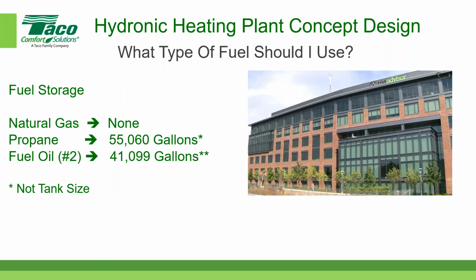And you get that information by talking to your propane supplier, because based on the amount of storage you want on site, they have a calculation, an app that they use to figure out what the size of the tank would be so that the propane creates a certain amount of surface area inside the tank so that it evaporates at the right rate, especially relative to whether the propane tank is buried in the ground or, in some cases, sitting above ground. That makes a huge difference on the evaporation rate. So the size of the tank can vary depending on where the tank is physically located, and it could be significant. Fuel oil doesn't have that problem.